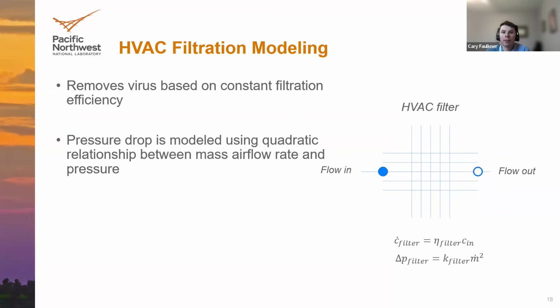And then the second key aspect is the pressure drop that the filter can impose on the HVAC system. This is really important for a couple of reasons. When I talked about that pressure airflow relationship being a key part of these air handling systems, moderate HVAC filters might have a smaller pressure drop or resistance imposed on the airflow of the HVAC system. But as you get to these more efficient HVAC filters, it can require significant power to push the airflow through these finer filters. And it can actually have a more significant effect on the HVAC operation, either just causing the fan to need to work really hard to push enough air through the system, or even resulting in reduced airflow rates.